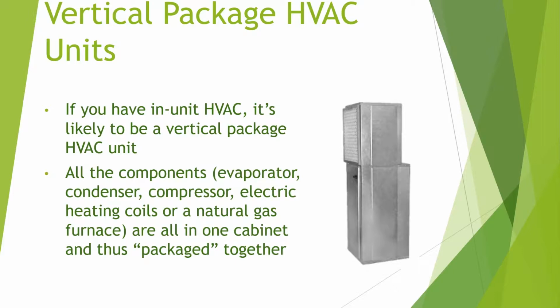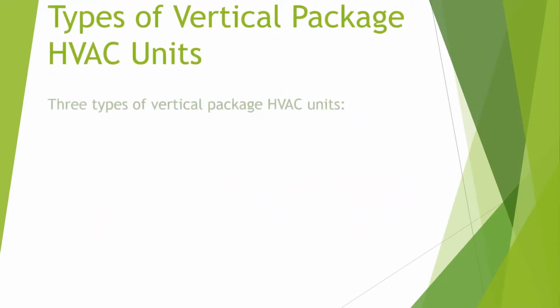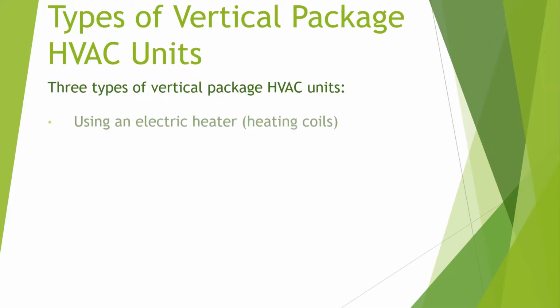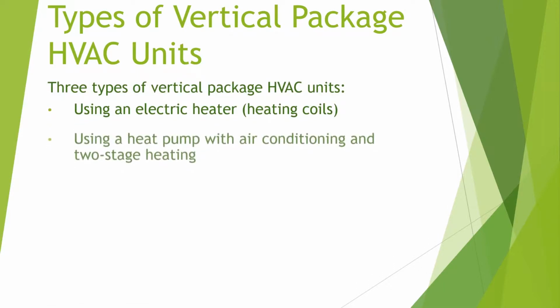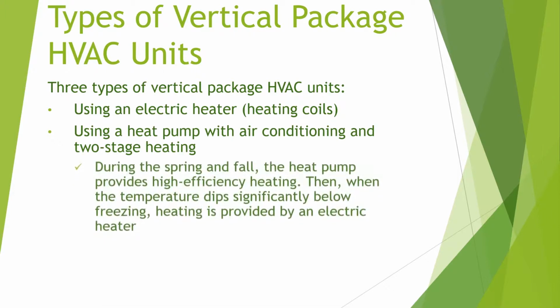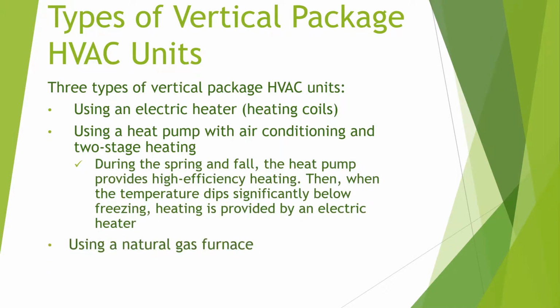Well, if all the components, the evaporator, the condenser, the compressor, the electric heating coils, or even a natural gas furnace, are all in one cabinet and thus packaged together with no outside apparatus. There are three types of package HVAC unit. One uses an electric heater with heating coils. The second type is using a heat pump with air conditioning and two-stage heating. During the spring and fall, heat pumps provide high-efficiency heating. Then when the temperatures dip significantly below freezing, heating is provided by an electrical heater. And the third type uses a natural gas furnace.